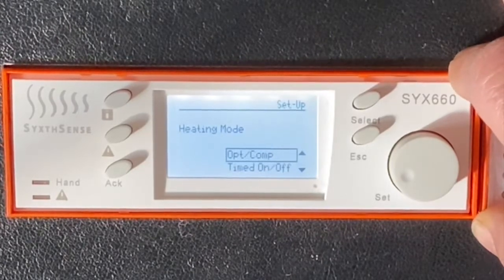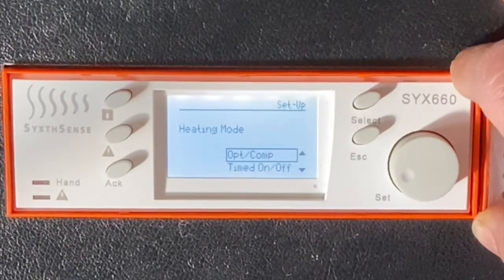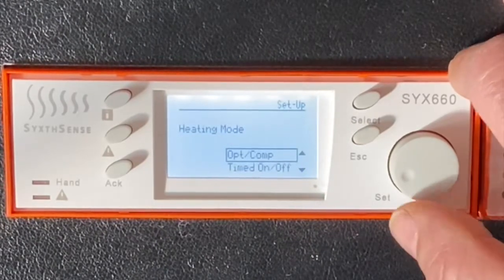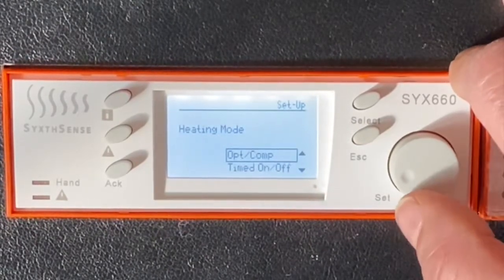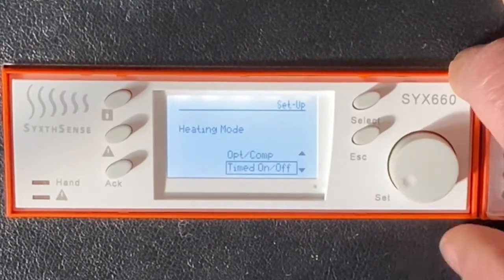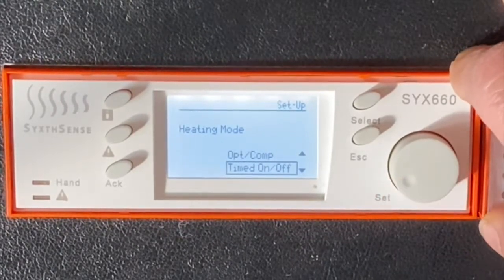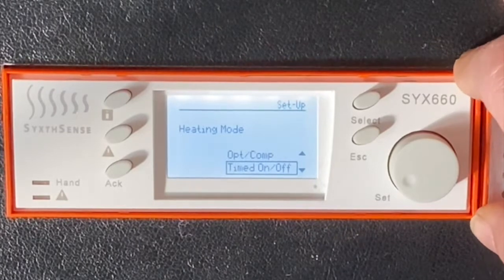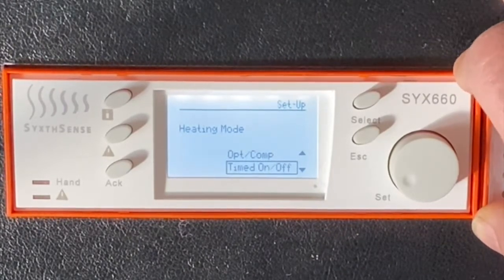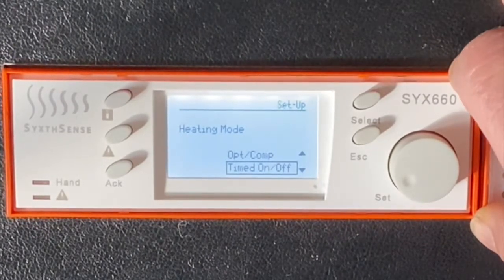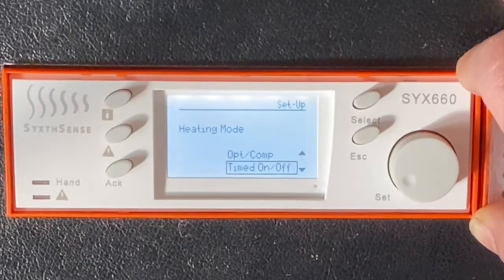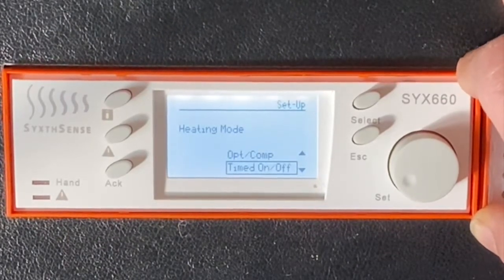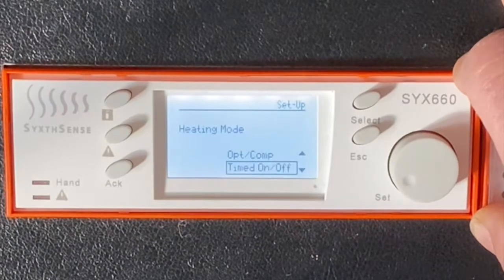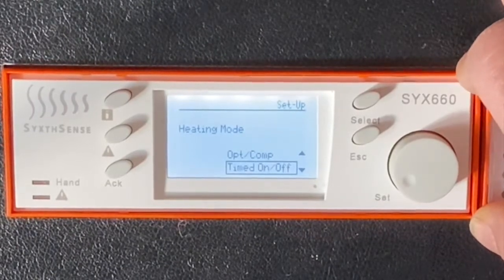Out of hours, we will return to a frost protection level, so the heating would technically be turned off, subject to going below frost conditions. Timed on off is slightly different to the optimum start. There is no optimum start capability, and out of hours the heating is returned to a frost condition, so we basically have more predictability about when the heating is going to start and stop.